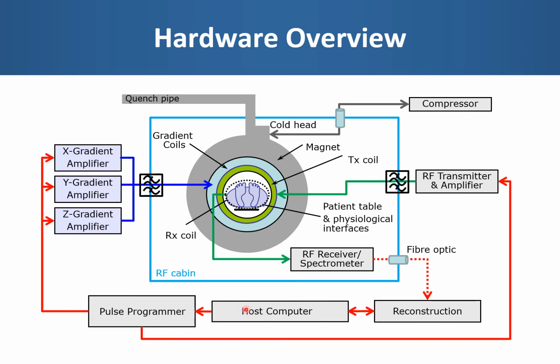The host computer communicates with a device called the Pulse Programmer that takes all the geometric information like the field of view, slice thickness, and calculates the desired gradient and RF amplitudes for those parameters. And it also handles the synchronization between the gradient pulses and the RF waveforms. The Pulse Programmer sends these waveforms and controls the timings to the amplifiers, which generate the very high voltages and currents required to drive the gradient coils. It also sends the digital RF waveforms to the RF transmitter and amplifier that generates the high intensity RF pulses, again through these filtered connections to the body coil.